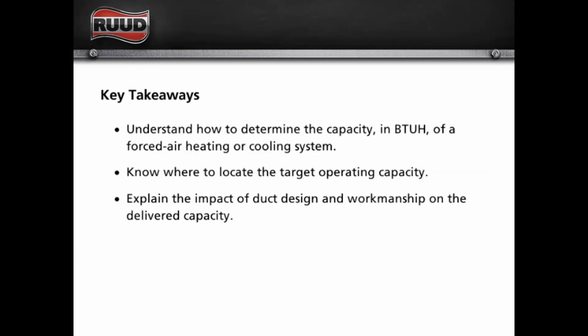So capacity calculation. And Nicole, I will email you this wet bulb to enthalpy conversion table when we're done here. But there's a couple of things that we have to do to measure capacity. We're going to check our static pressure. We're going to compare that static to our blower table because we have to know exactly how many CFM we're moving, not rated airflow, actual airflow. And then we're going to check some temperatures. We're going to check wet bulb temperature in our return and wet bulb temperature in our supply.